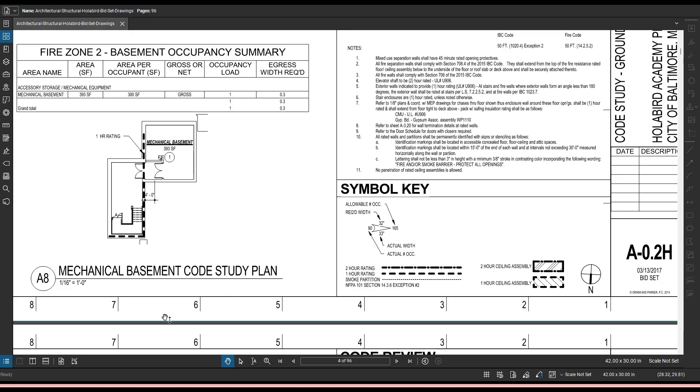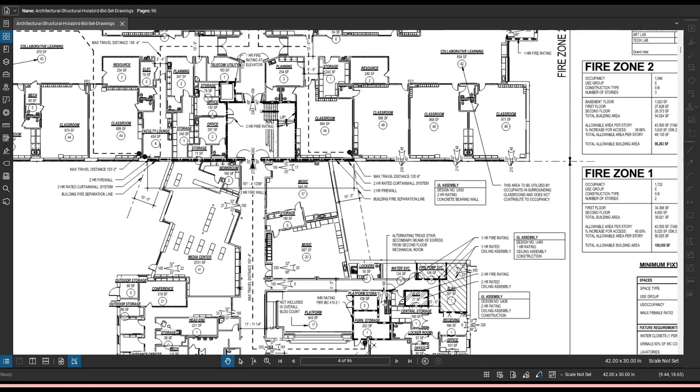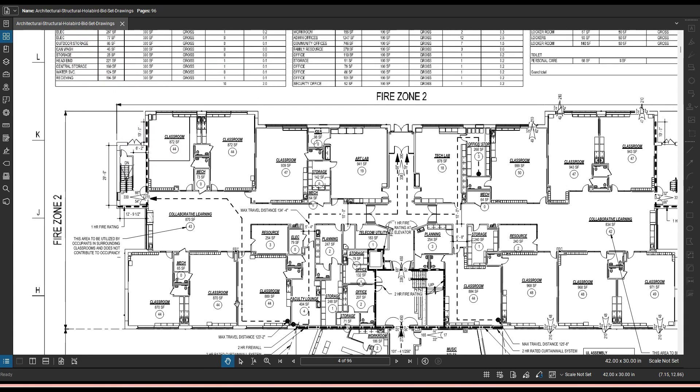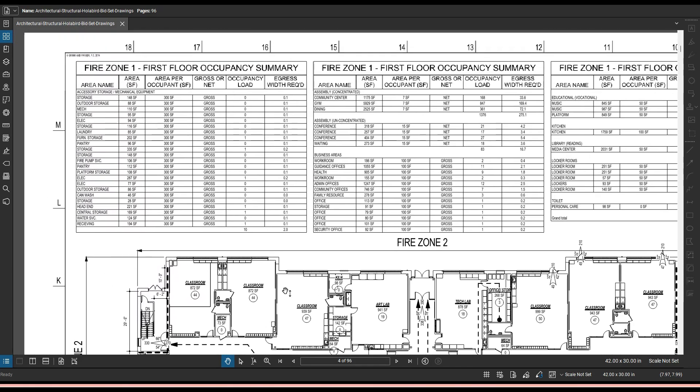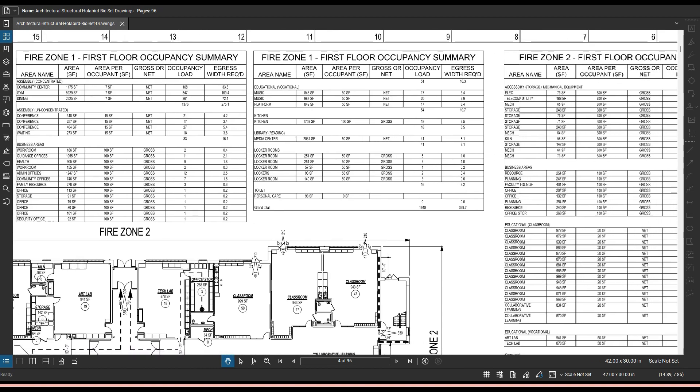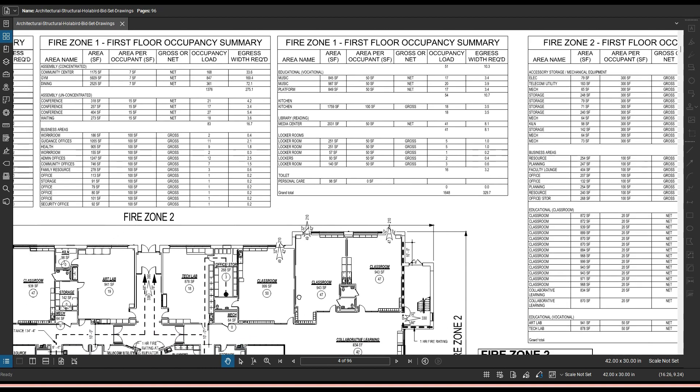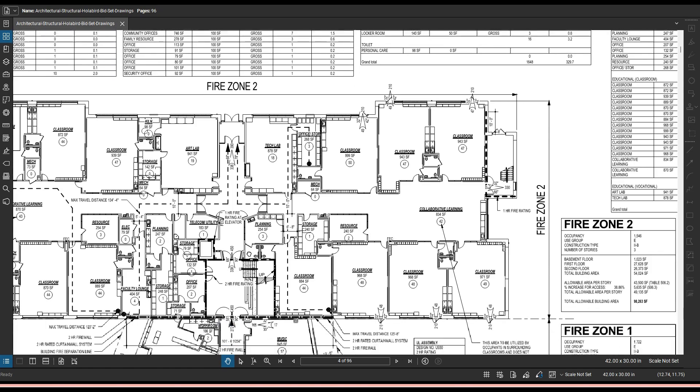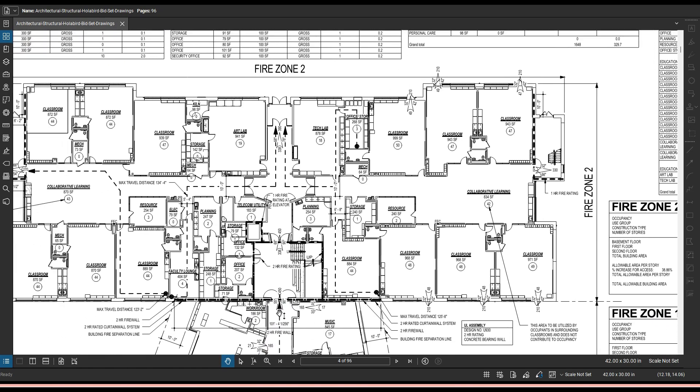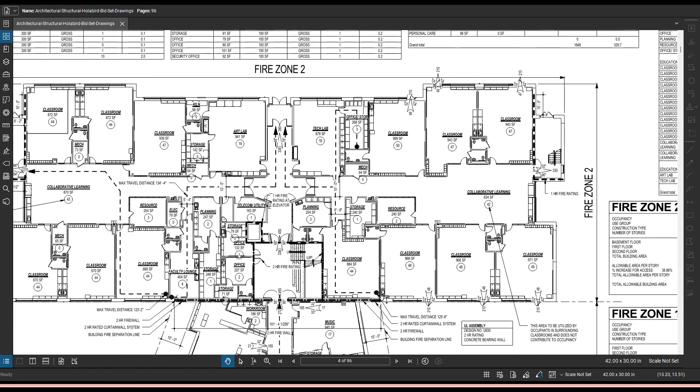So let's move on. These charts up here give somewhat of the same information that we've seen in similar formats. So I want to more so focus on some of the things that you see written on the plans. Let's take a look at one of the things that we saw when we were looking at the code review. It said something about max travel distance. So in this corner, if you were standing in this corner and there was a situation where you needed to get to the exit, let's say a fire, part of the code review ensures that you don't have to travel very far to get to the nearest exit. So the max travel distance is 125 feet and 8 inches, meaning that all of this adds up to when you get into the door, you would have gone 125 feet and 8 inches.